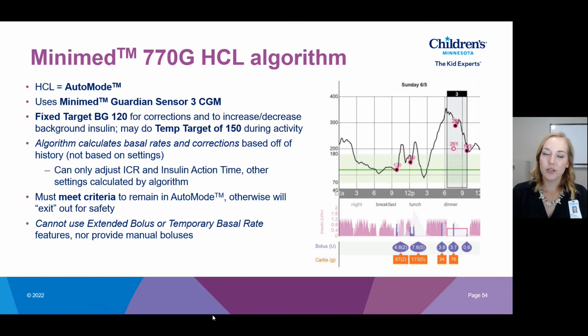In auto mode, you cannot use the extended bolus or temporary basal rate features, and you also can't provide manual boluses. Now, if you're new to pump therapy, you don't really have to worry about this. This is more so for current pump users that do manually bolus. Essentially, what that means is if you enter your blood sugar and your carb count into the dose calculator, and it calculates a number that you think you need more or less than, you can't override it and change it. It's not a bad thing that you can't do that.